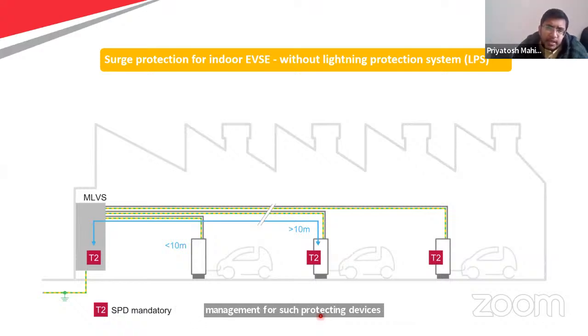The IEC standard says you should have a surge protecting device within a distance of at most 10 meters. If you have a charging point and up to 10 meters from that point there is no surge protecting device, this is wrong and not allowed. That is the way of placement for surge protecting devices.